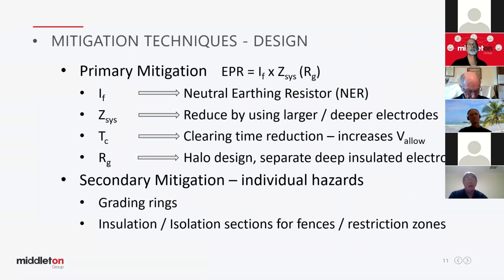So now we've seen that we can measure our EPR, and if you remember back to the graph of our fellows working in the substations, we can measure the voltages on the fences there. We then compare the voltages we measured and scaled up with the allowable voltages we calculated earlier, and we might find that we've got some voltages on some fences, or transferred out away from the substation, that are above the allowable. So what are we going to do about it? Well, our job as designers obviously is to mitigate those hazards, to bring them down to what we term negligible, and which is acceptable to society.